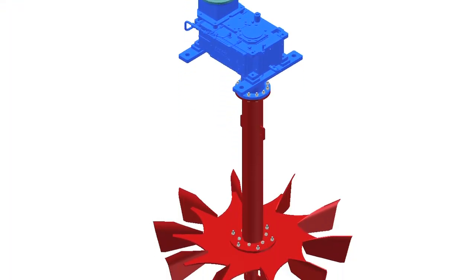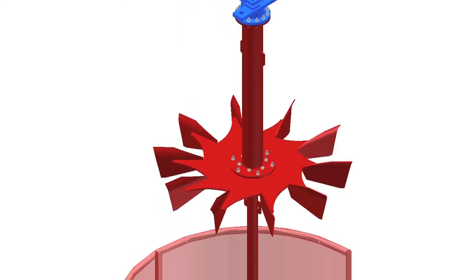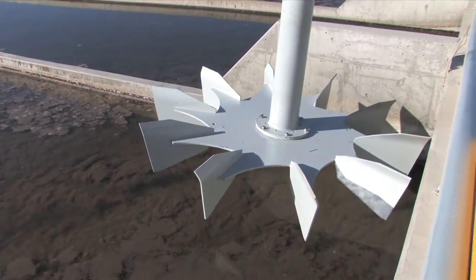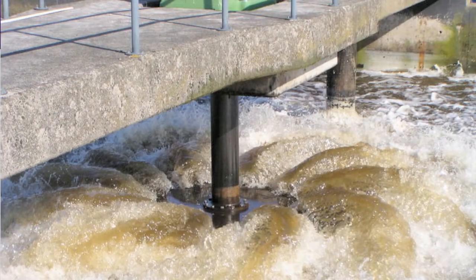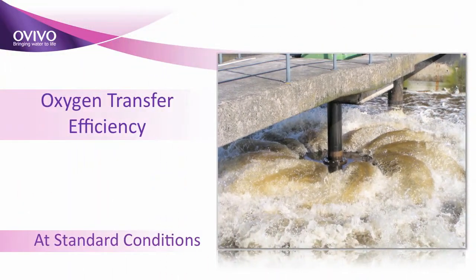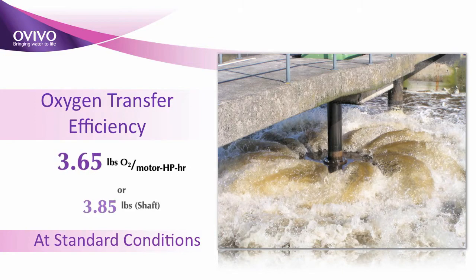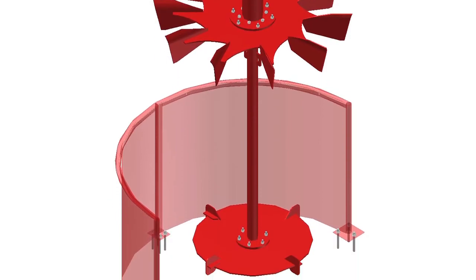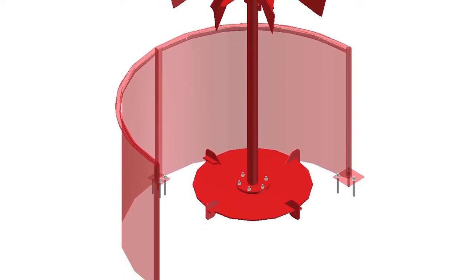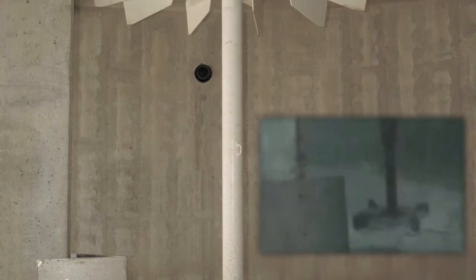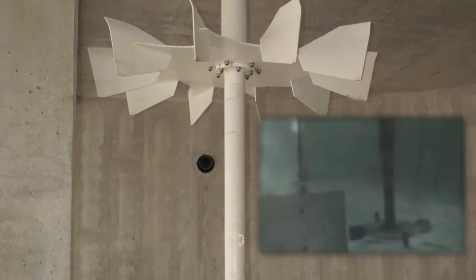Designed for both aeration and propulsion, the accelerator is the most efficient carousel system aerator on the market today. The specially designed surface aerator provides a minimum oxygen transfer efficiency of 3.65 pounds of oxygen per motor horsepower hour. The optional lower impeller allows for a deeper basin design and optimal flow loading turndown capabilities while still maintaining floor scouring velocities throughout the basin.